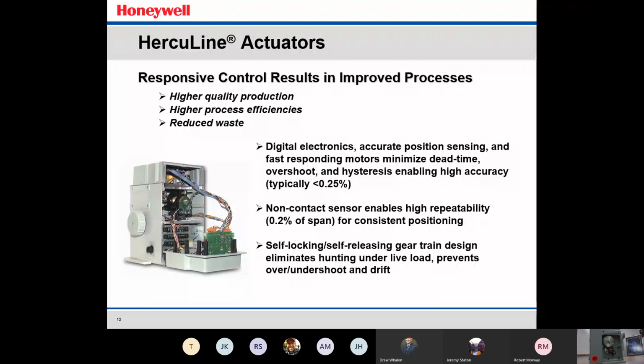We talked a little bit about the digital contacts. I probably won't dive into this slide other than just saying that the contact sensing or the non-contact sensor provides feedback to the control system. It has very high repeatability, consistent positioning, and it is night and day when you compare it to a slide wire feedback that some of the older style position proportioning systems have. So it'll give the system very high accuracy on where the true position of that actuator is.